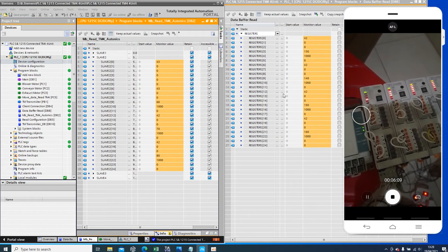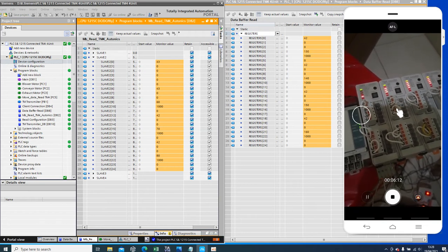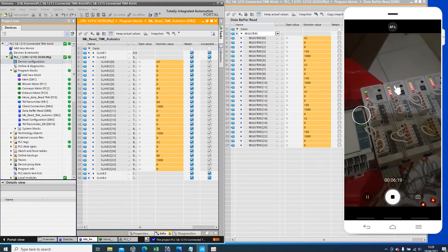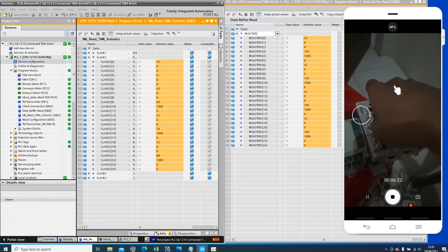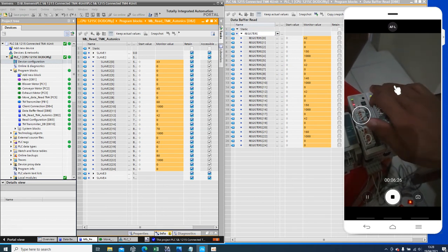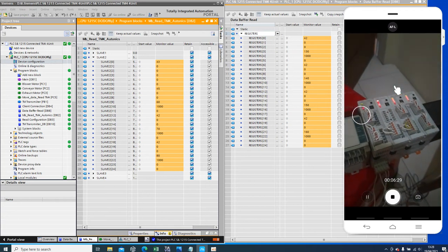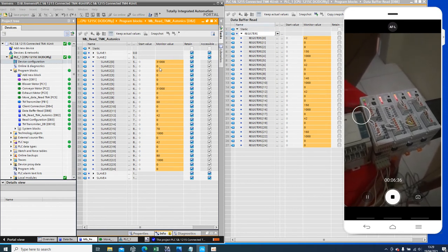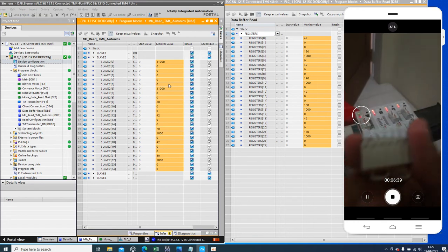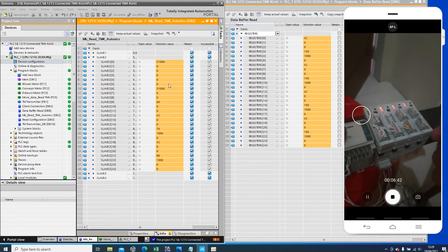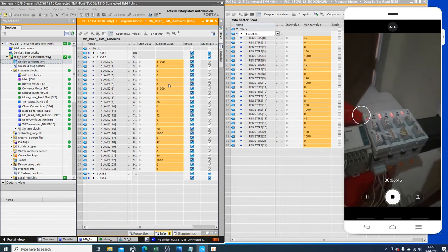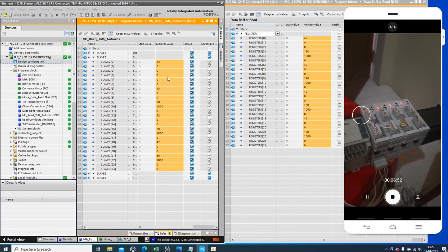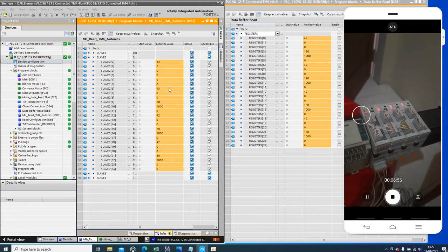Now I want to make sure that sensor — here sensor 1, sensor 2, sensor 3, sensor 4. Take sensor 1 and sensor 2 from this connector, from this module, using slave 2. I will connect it — it's very difficult. The status will be changed: 2-channel sensor, meaning the slave doesn't have a sensor anymore. I will connect it again. The status will be changed — actual temperature is 43 degrees and 43 degrees.